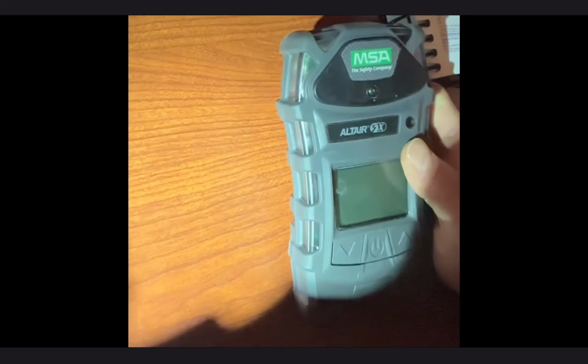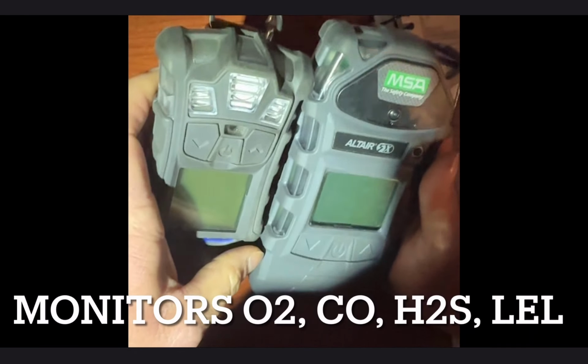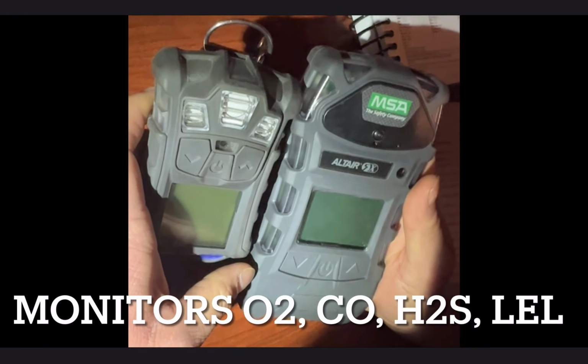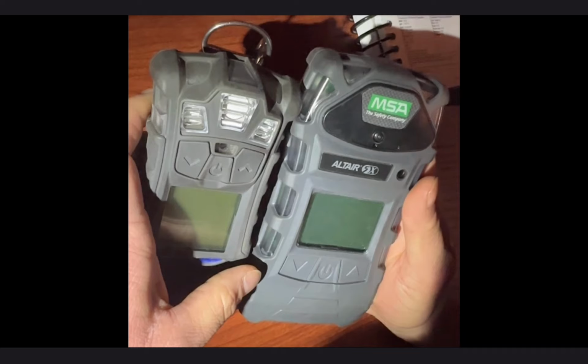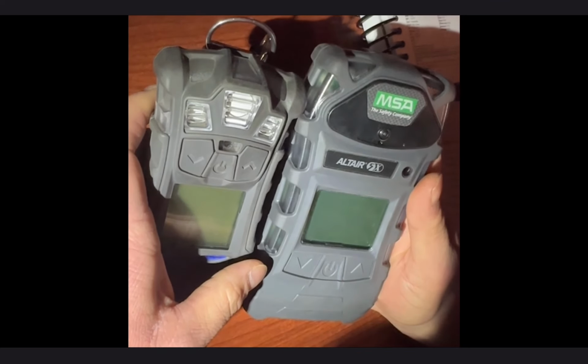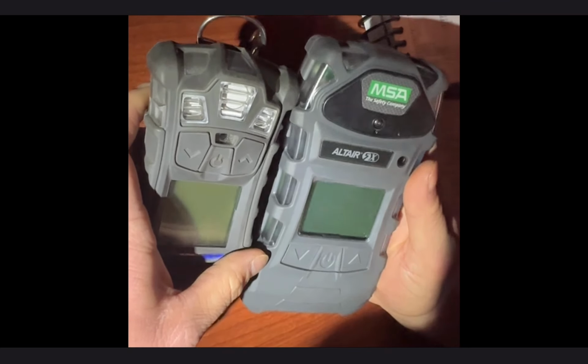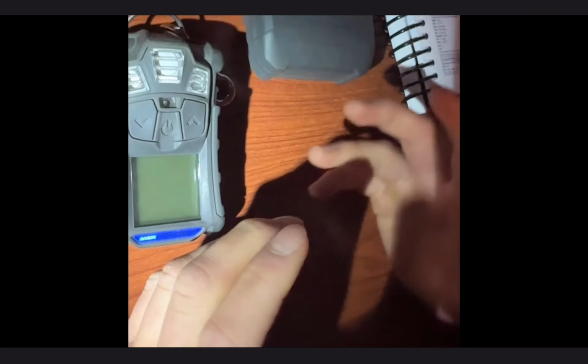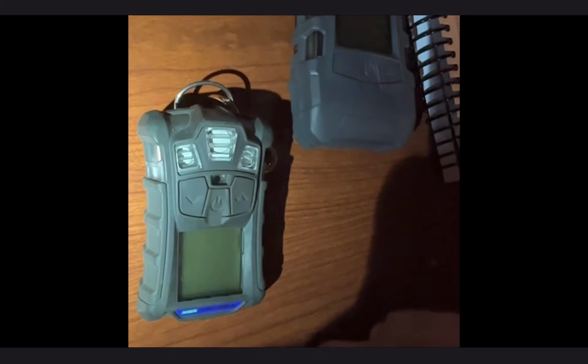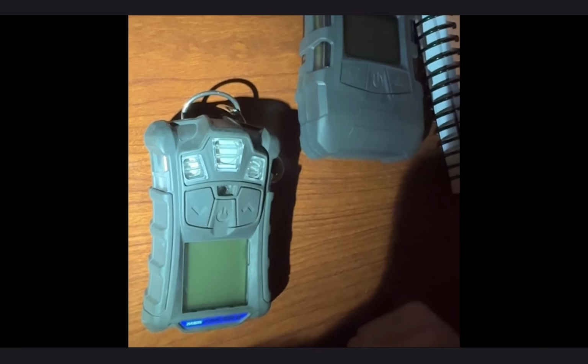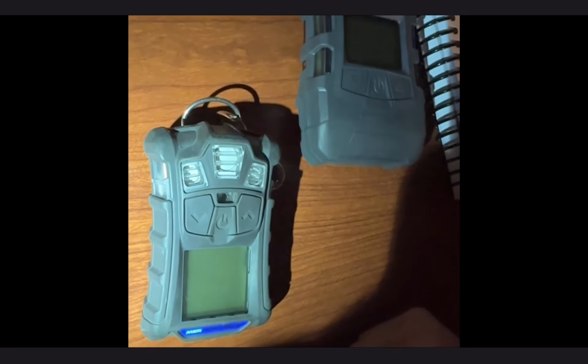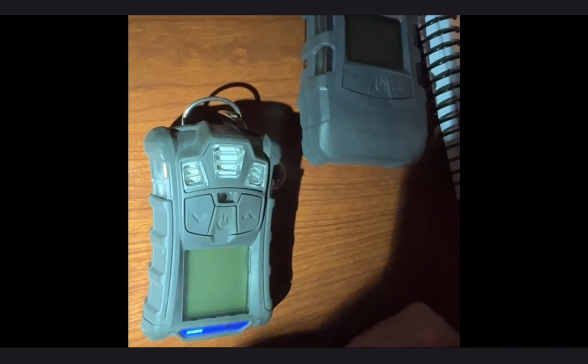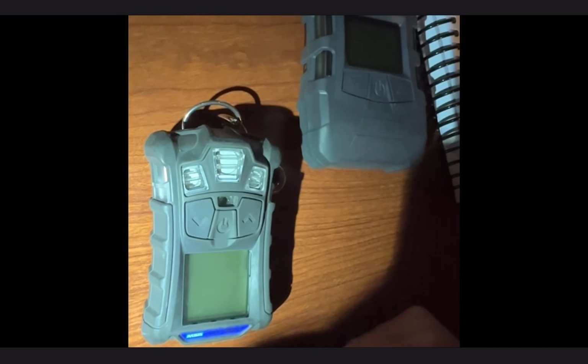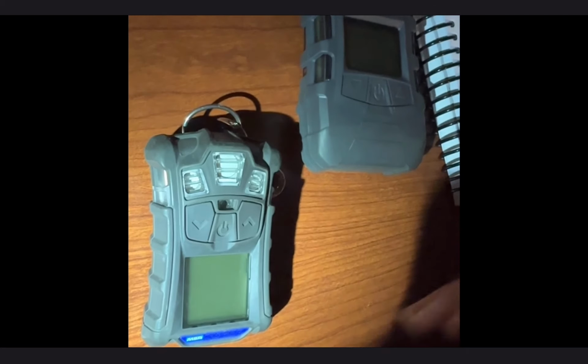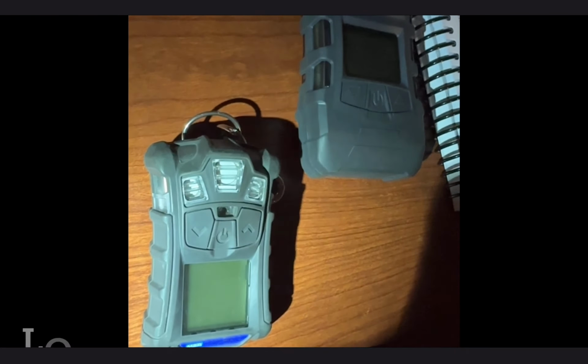So, like I said, these 2 monitors have the same sensors in them. They both have 4 sensors. Those sensors monitor O2, CO, H2S, and LEL. On the oxygen side, the sensor range itself is from 0 to 30%. On the CO, it's 0 to 1,999 parts per million. On the LEL, it ranges from 0 to 100%. And on the H2S, it ranges from 0 to 200.